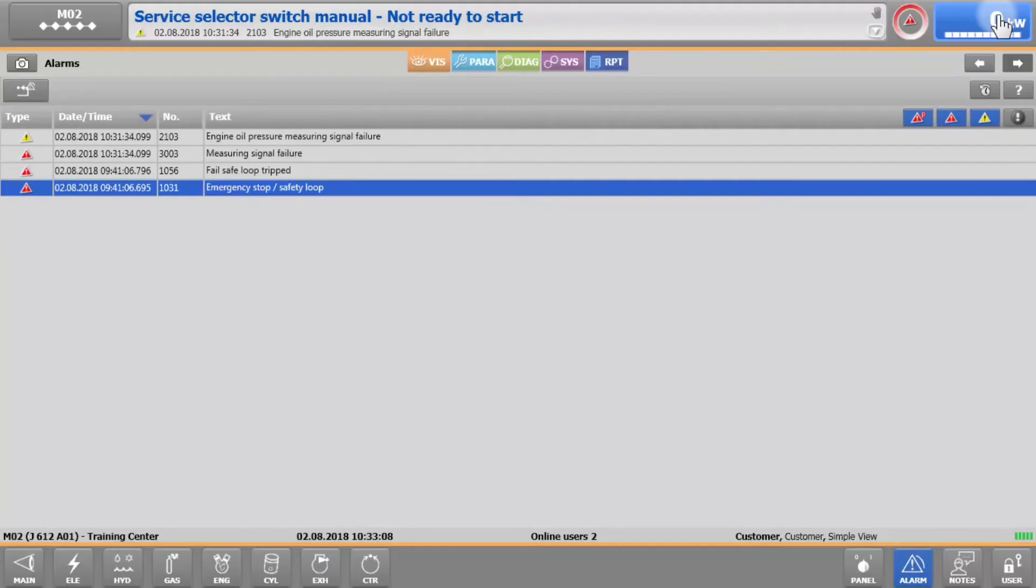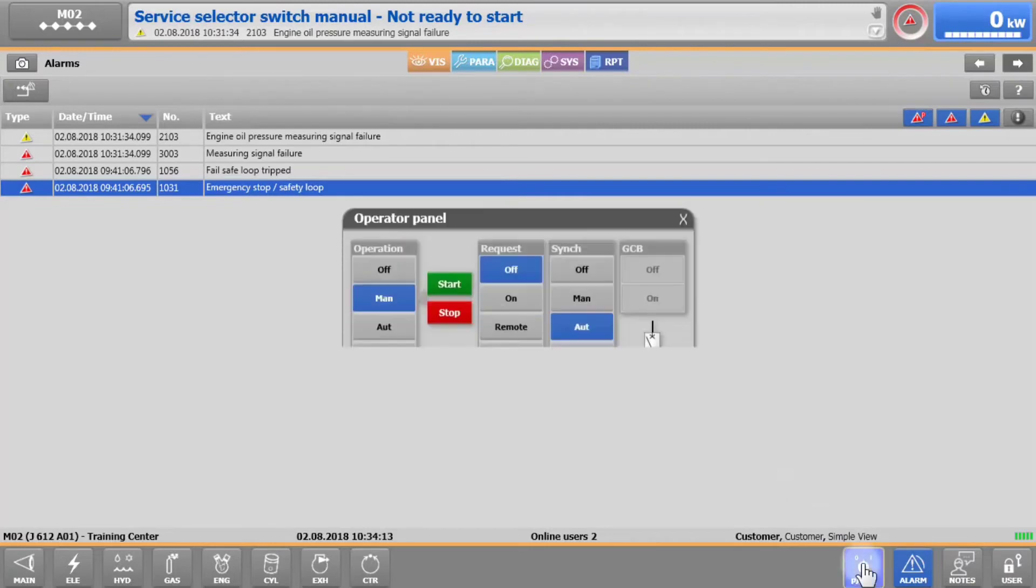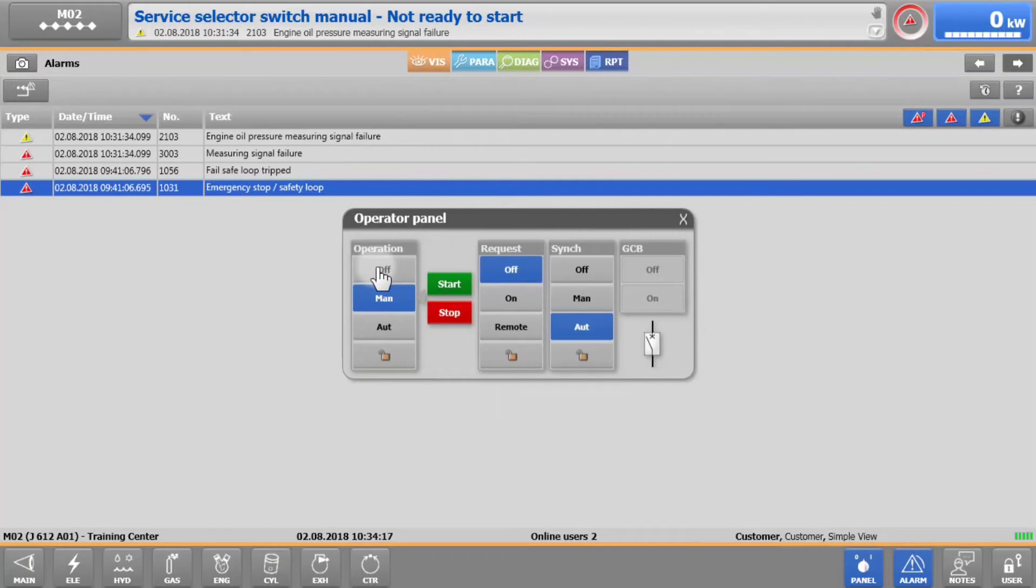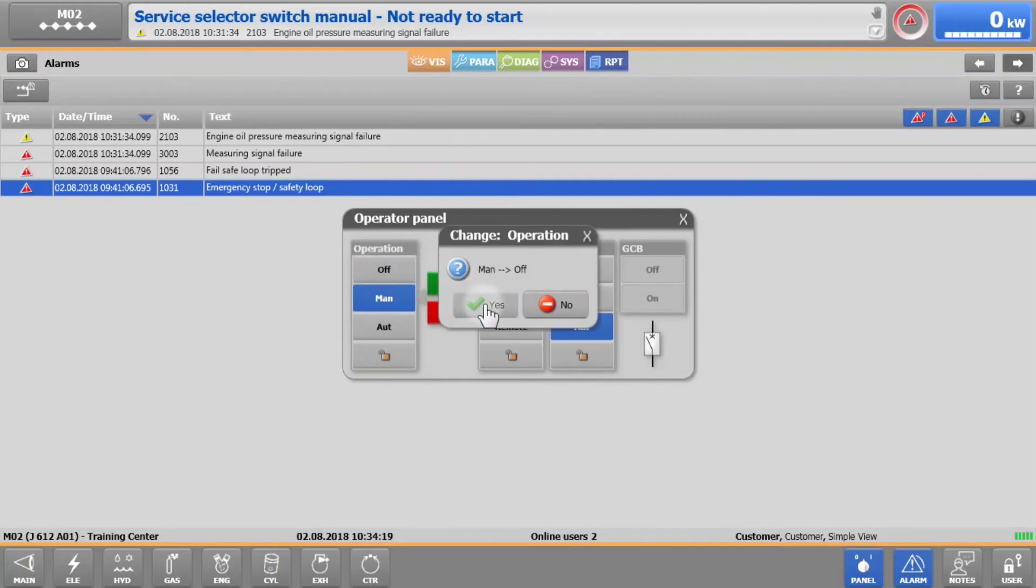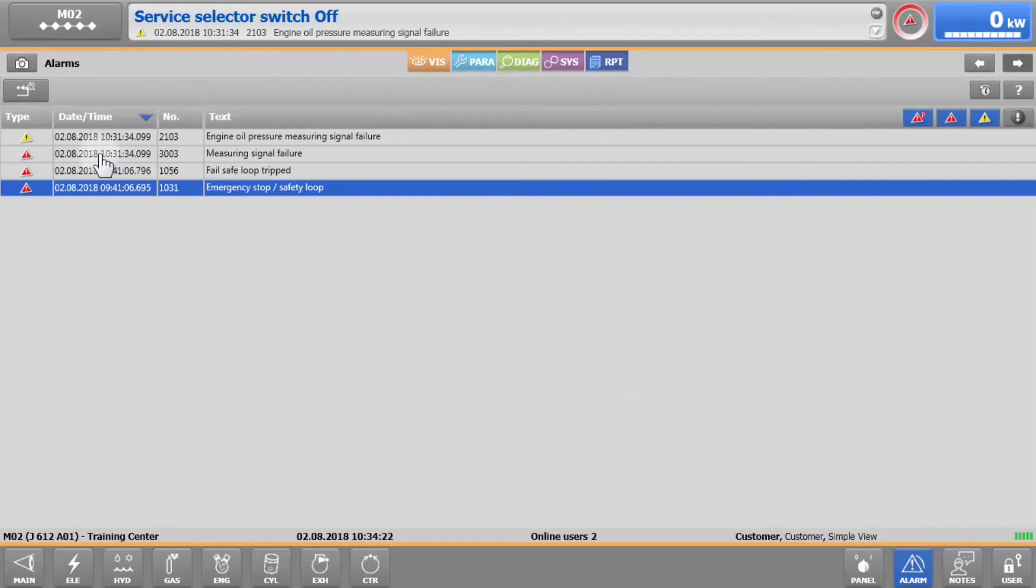Once the cause of an alarm or warning has been identified and resolved, it can be reset in X-T4. To reset an alarm, it is mandatory that we are logged in and that the operation switch is in the off position. The alarm can then be reset by tapping on the reset button in the top left corner of the screen, below the camera symbol.